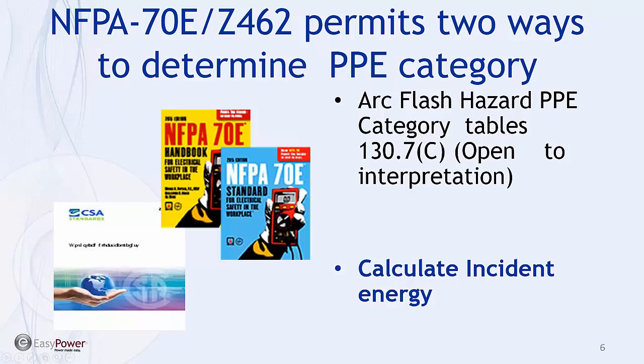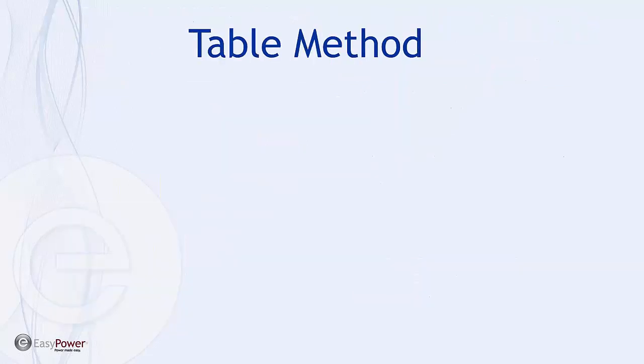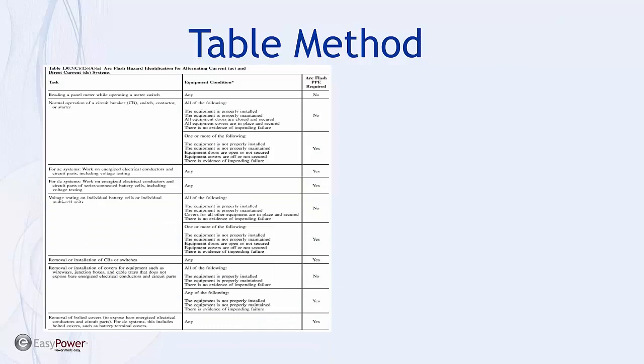With the advent of NFPA 70E 2015, there are basically two ways to determine PPE category. There are the arc flash hazard PPE category tables, and here they're not talking about HRC, they're talking about PPE category tables. That's one method. The second method is to calculate incident energy. Previously we combined these two and used incident energy to look up the PPE category table, calling it the HRC table. Now there's a separation of those two items.